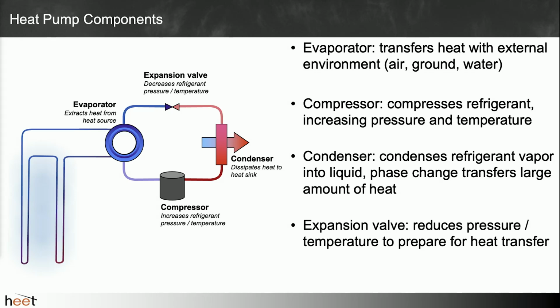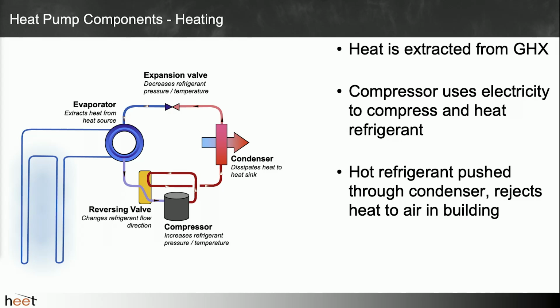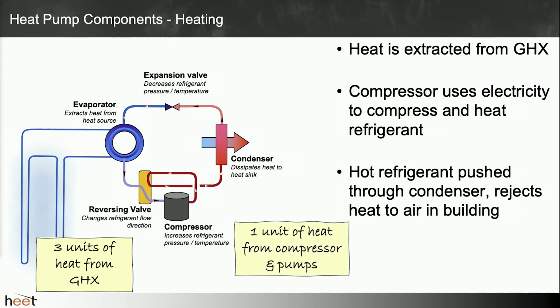So our ground source heat pump in heating, again, we have this reversing valve, which differentiates our fridge from our heat pump, so we can also do heating. It'd be strange if a fridge did heating. But we extract heat from our ground loop, where we have 3 units of heat coming from the ground. We have our compressor, which uses electricity to compress and heat the refrigerant.